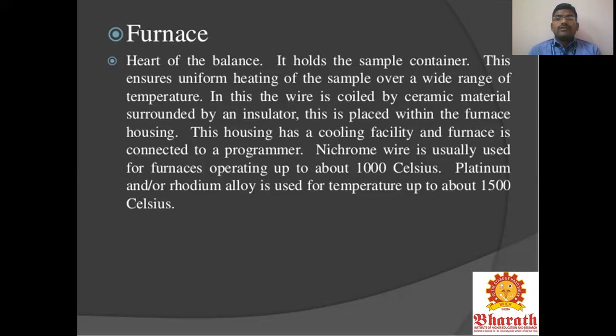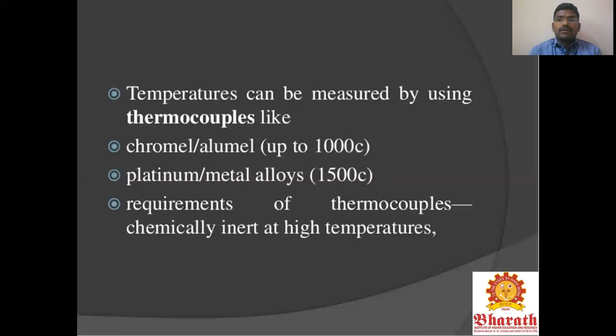The temperature can be measured by using thermocouples like chromel-alumel up to 1000 degrees Celsius. Platinum metal alloy is used for 1500 degrees Celsius. The requirements of the thermocouples are that they be chemically inert and suitable for high temperature. You also have to record the thermoanalytical methods. The recorder provides a continuous record of the sample weight as a function of temperature. There are two types of potentiometric recorder.